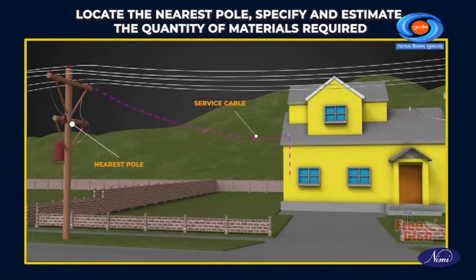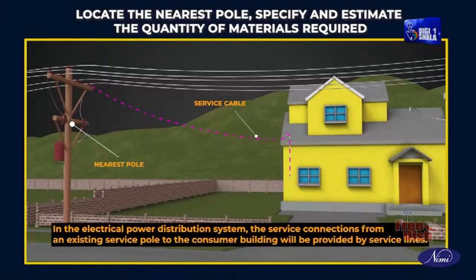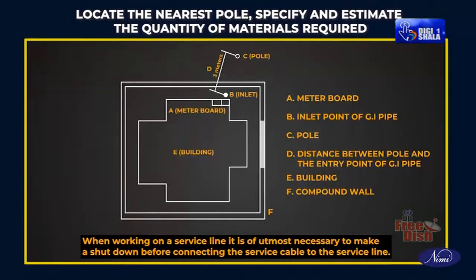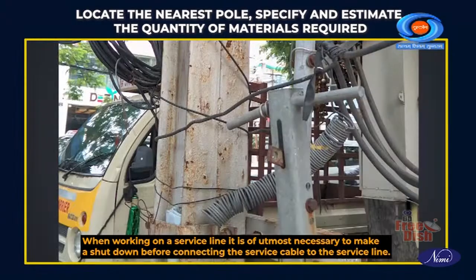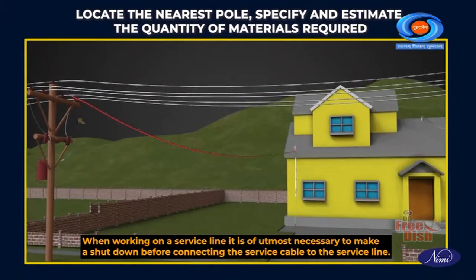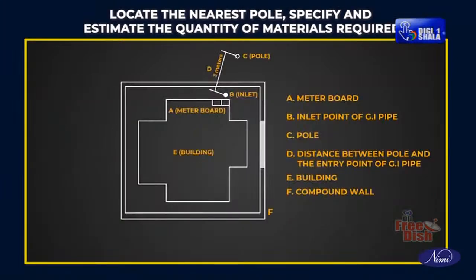Locate the nearest pole, specify and estimate the quantity of materials required. In the electrical power distribution system, the service connections from an existing service pole to the consumer building will be provided by service lines. When working on a service line, it is of utmost necessary to make a shutdown before connecting the service cable to the service line. Now, let us start our exercise.